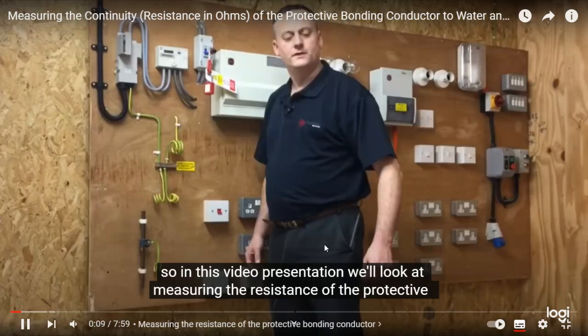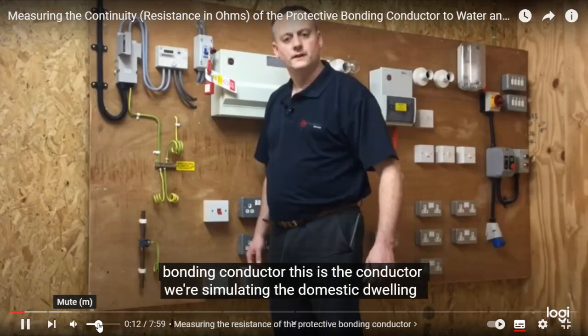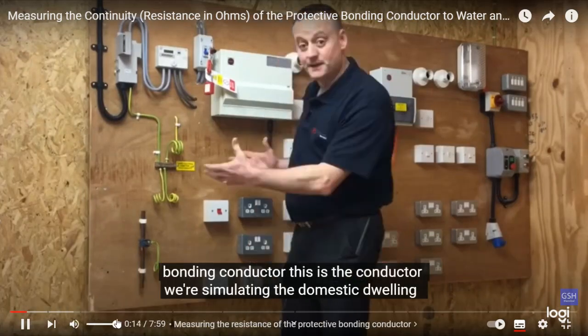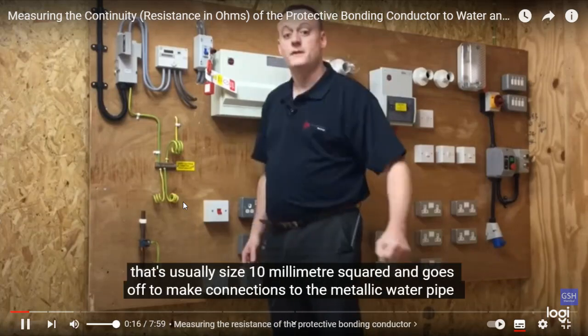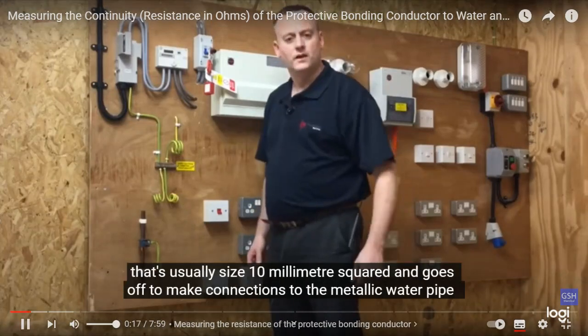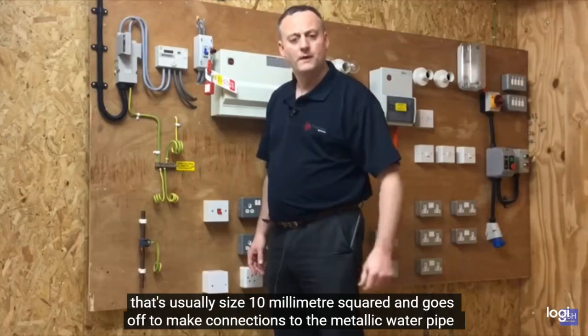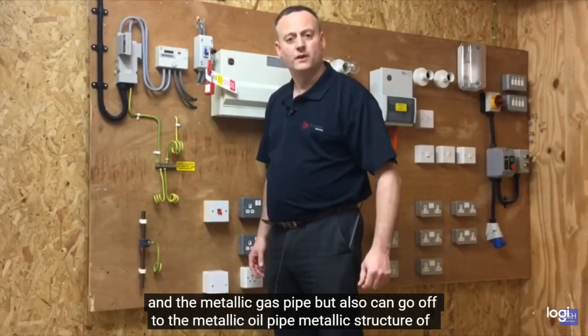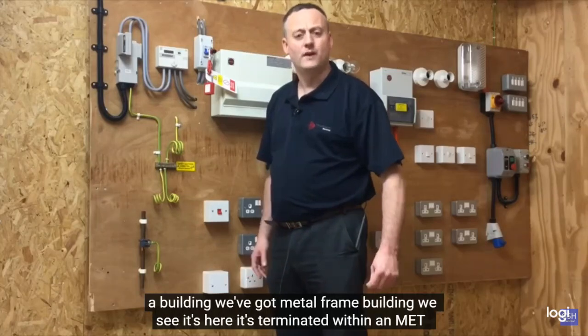So in this video presentation, we're going to be measuring the resistance of the protective bonding conductor. This is a conductor within something like a domestic dwelling that's usually sized 10 millimetres squared and goes off to make connections to the metallic water pipe and the metallic gas pipe, but also can go off to the metallic oil pipe, or the metallic structure of a building. We've got a metal frame building.